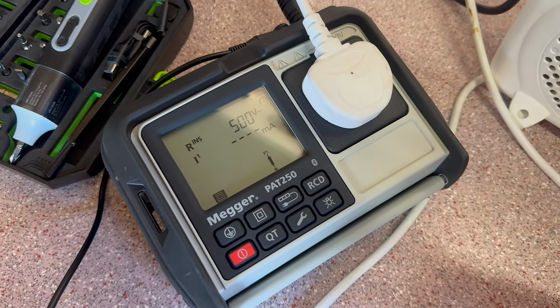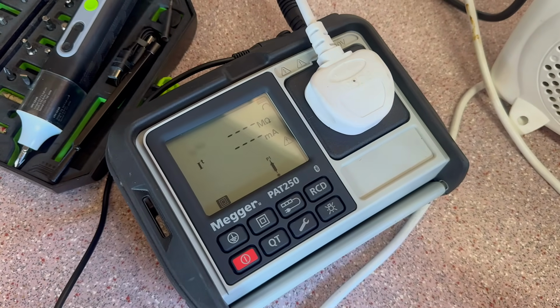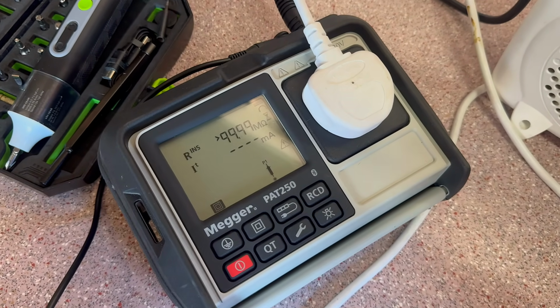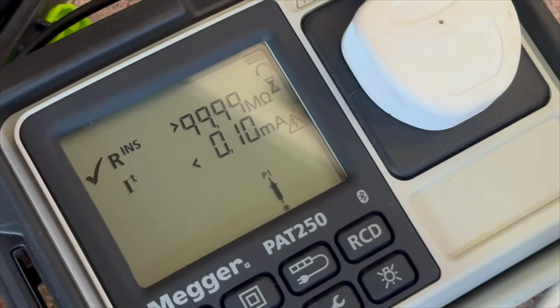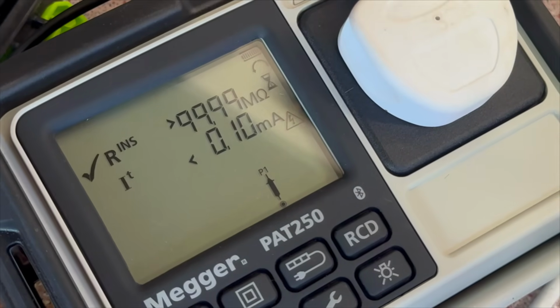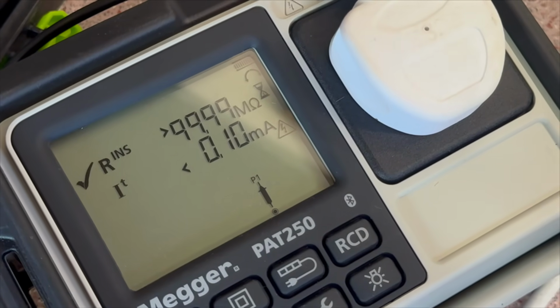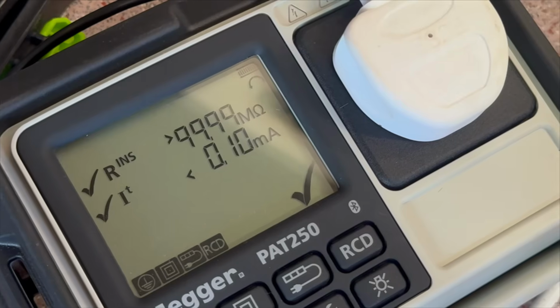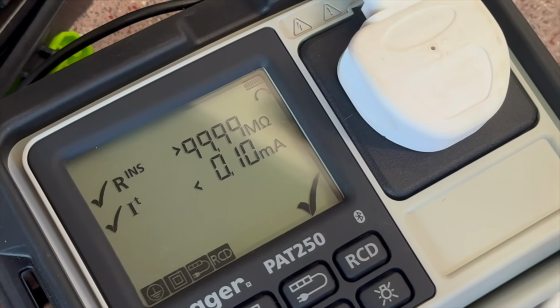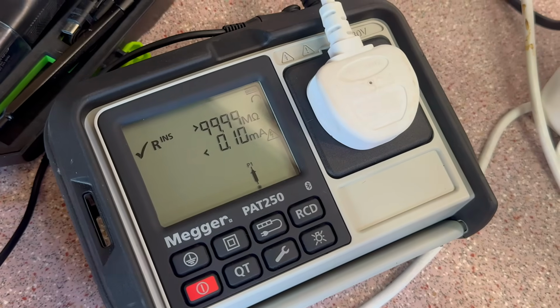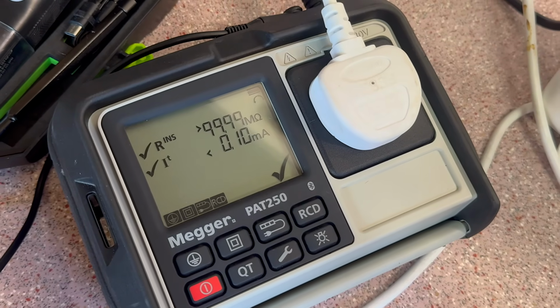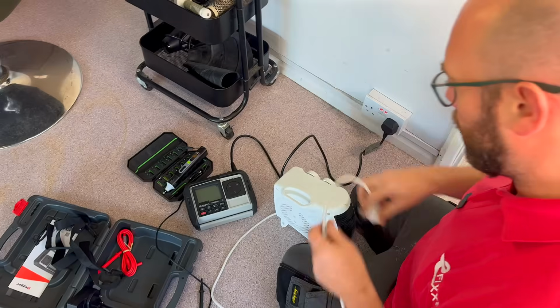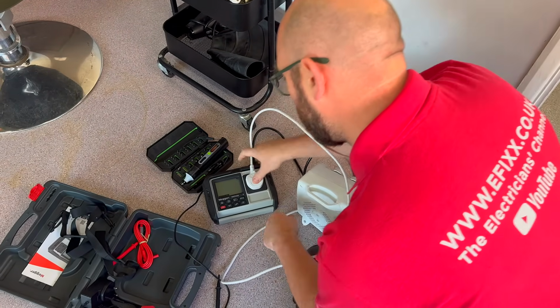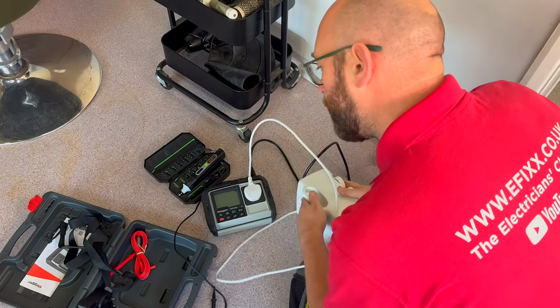The tester will automatically test between live conductors and earth, and connecting the probe onto the appliance will pick up any breakdown in insulation. I also carry out a leakage test. The PAT250 needs to be plugged in for this because we are putting a voltage on the device to see if it works and if any leakage current appears. This gave a leakage of 0.1 milliamp, which is more than okay, but be aware this device will go live, which is why the tester requires additional prompts to make sure you know it's safe to proceed with the test.